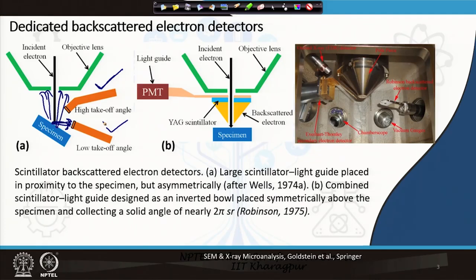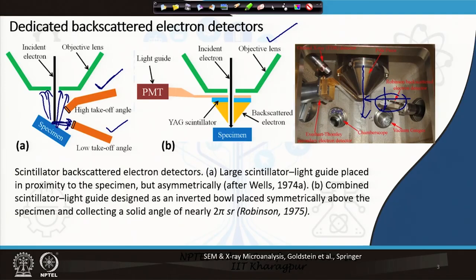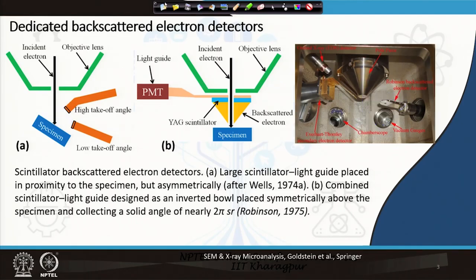In most cases we have the arrangement shown in figure B. There is a flat type of detector which can be moved or pushed so that it is positioned just below the pole piece. In the center there is a hole through which the electron beam passes and strikes the specimen. The backscattered electrons that emerge are collected by this backscattered electron detector. Because backscattered electrons have higher energy, if we use an acceleration voltage of approximately 10 kV we have a sufficient number of high-energy backscattered electrons, and for that case we do not need to apply a bias to the scintillator in the detector.